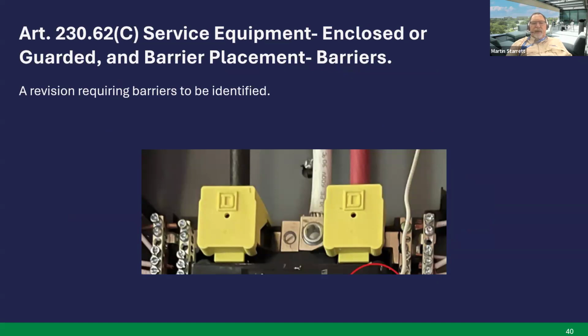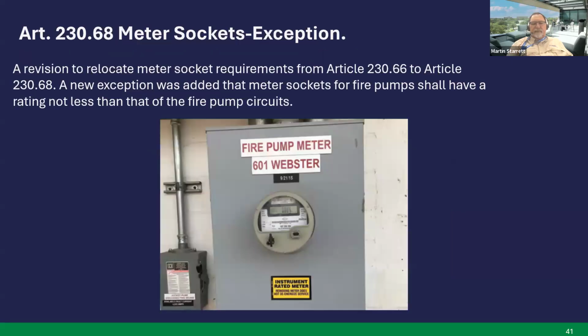Article 230.62(C), service equipment enclosed or guarded and barrier placement. Barriers only have to be identified. Article 230.68, meter sockets, an exception to that article. A revision to relocate meter socket requirements from Article 230.66 to Article 230.68. The new exception was added that meter sockets for fire pumps shall have a rating of not less than that of the fire pump circuits.